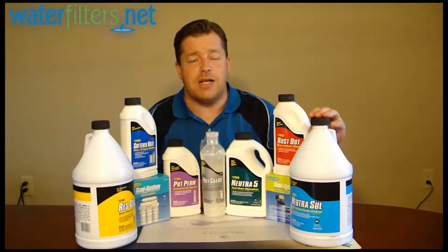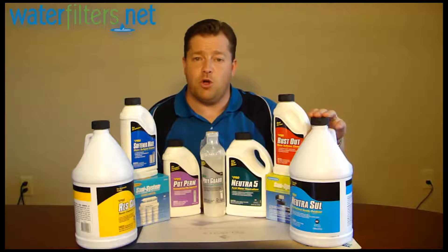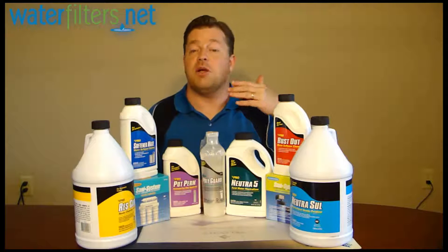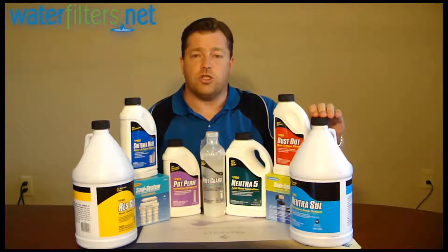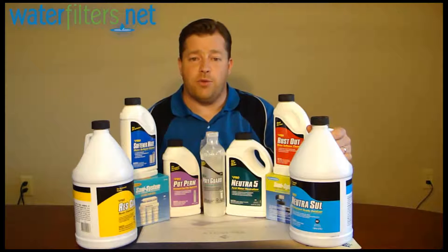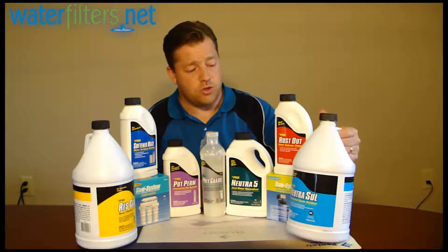Over here we have NeutraSul. NeutraSul is a 7% hydrogen peroxide solution. It is also a strong oxidizing agent and is commonly fed into the water through a chemical feed pump. One of the most common uses for it is in situations where there's a hydrogen sulfide problem. Hydrogen sulfide smells like rotten eggs — some people call it sulfur smell — and it requires a strong oxidizing agent to get rid of that nasty odor. It can also oxidize some other things depending on the specific water chemistry.